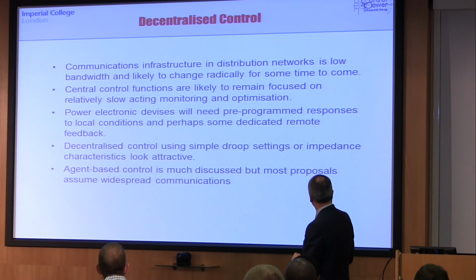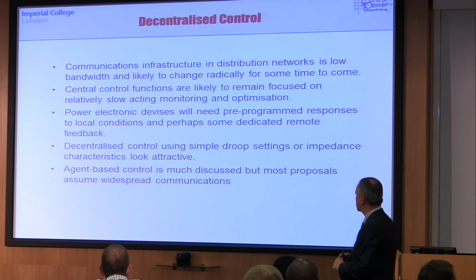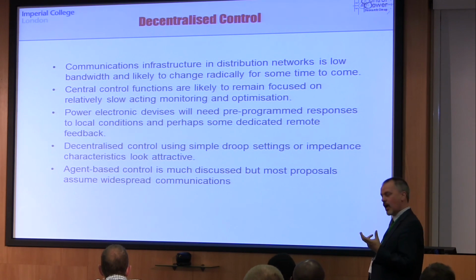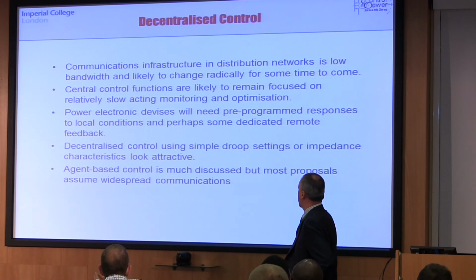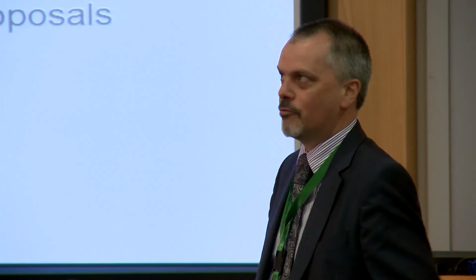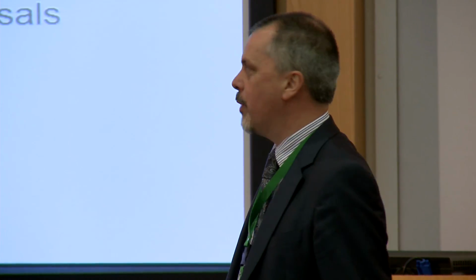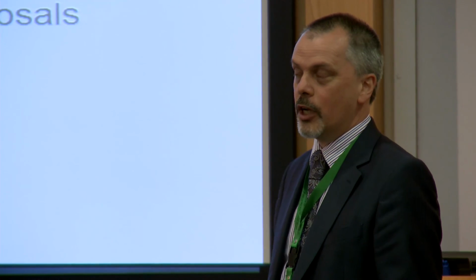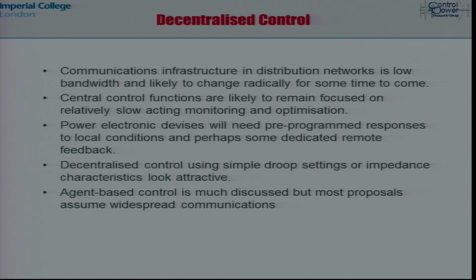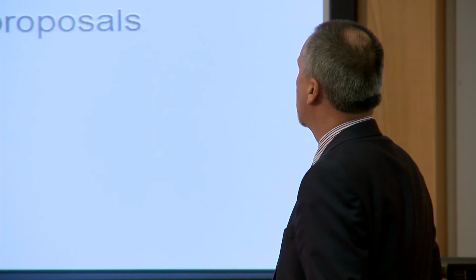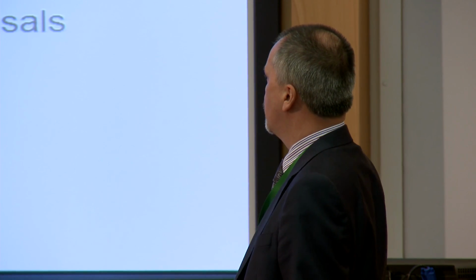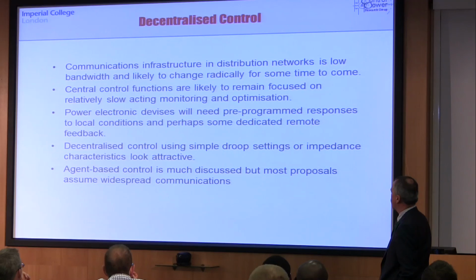Quick sort of penultimate slide, I think. Just a few quick words about control. Distribution networks have very little infrastructure for monitoring and communication at the moment, and there seems still to be a resistance to rolling out, measure everything and make it available. We are going to have to live in an environment for some time where communication back to the central control room is on 10-minute intervals and is for monitoring and for optimizing the network configuration, not for closed-loop control. So the services to the network have to be on the basis of local control loops using mostly local measurements and perhaps some dedicated remote measurements. So decentralized control methods based around droop settings and impedance presentations, I think, look attractive.